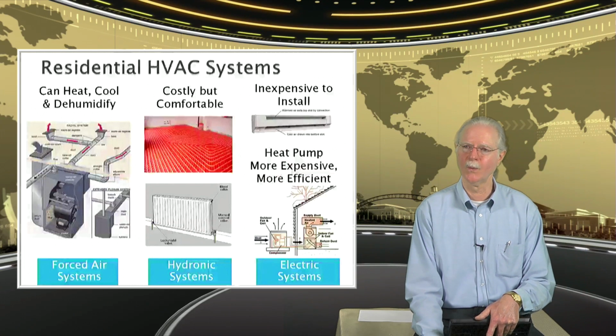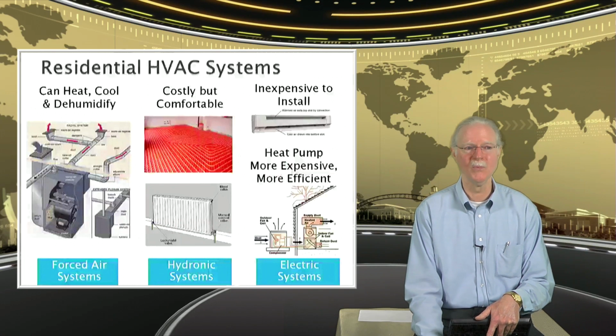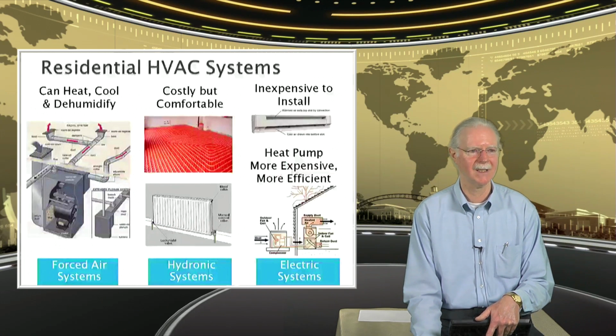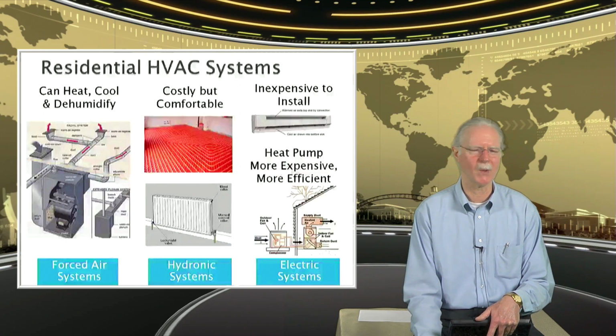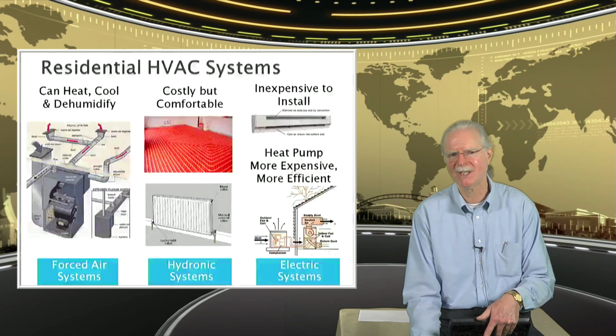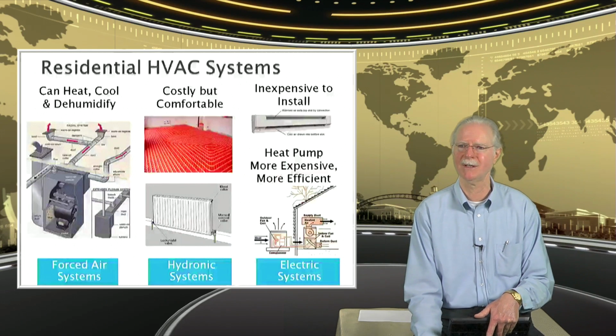With a heat pump, we're removing heat from the outside air on the outside and moving it to the inside air. And what really is the big difference is the temperature differential between the two. Because with an air conditioner, how much temperature differential do we have? Maybe 15 or 20 degrees. If we're moving from the outside to the inside, how much temperature differential do we have?